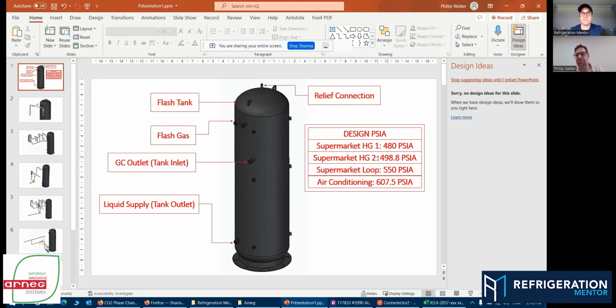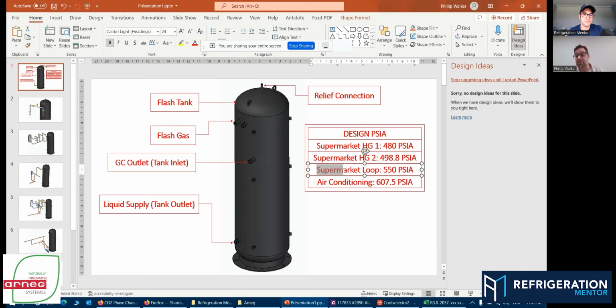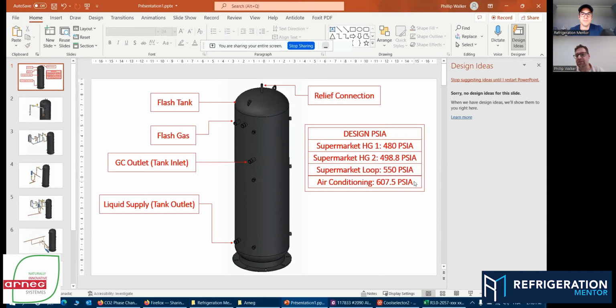When we start getting into a supermarket, we're in the basement and the evaporators are slightly above us, so we're going to raise that flash tank. What we're doing is creating a greater pressure differential for everything moving in the system. So this is what we work with. If we're doing a loop system with electric defrost, our flash tank is going to be around 550 PSIA. And I would say between these two, it's fairly standard as we've seen in the industry.